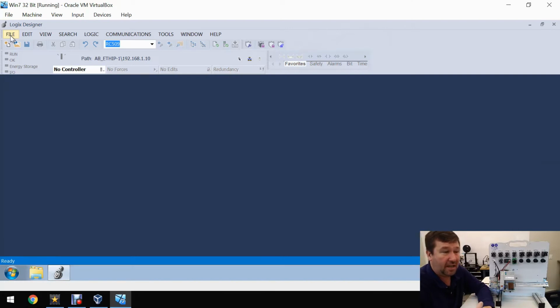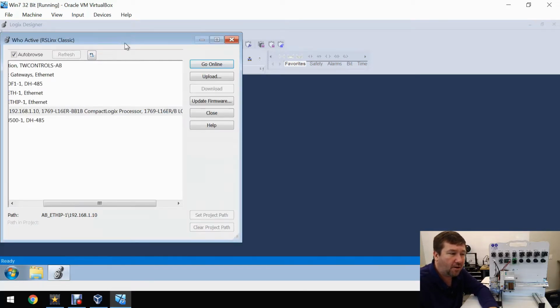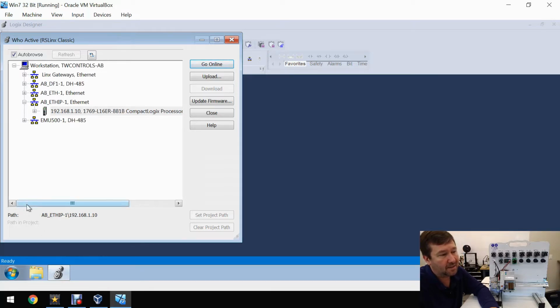So we're going to be starting out in Studio 5000 with no program open, and we're going to go to Communications and Who Active. Now there is an upload button right here, but I like the Who Active, especially as you're getting familiar with it, because it gives you all the options and it lets you make sure you're navigating to your PLC. So we're going to be using the Ethernet IP driver, and we're going to select the PLC, and then we're going to click this upload button.